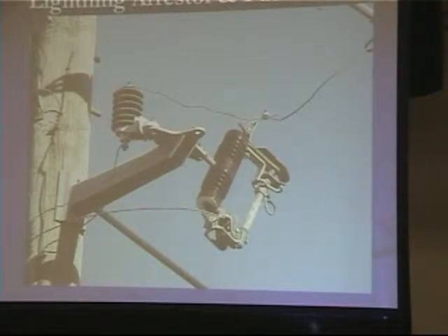The other piece there is a fuse, is that right? That's a fuse, yeah. Those will be opened and closed as they need to open up and close a line so they can take sections off the line. The lightning arrestor is there for lightning. The fuse cutout is basically there for the human to come open and close. I thought those dropped if there was an overload in the circuit. It can, that's not the actual intent for them, but it's kind of a backup to the lightning arrestor. So you have a hinge at the bottom of that rod, and you just pull, and it pulls away.